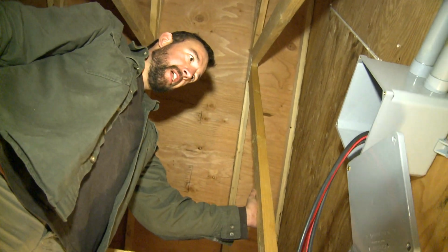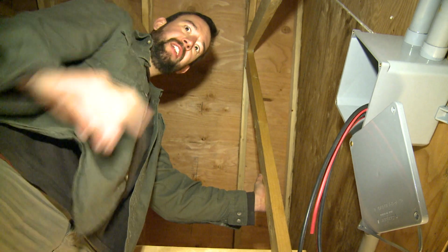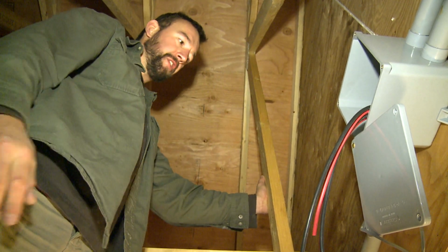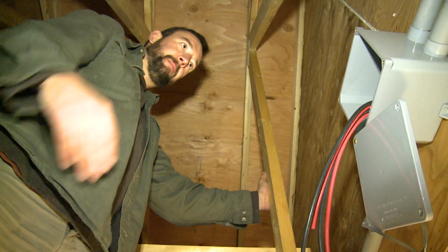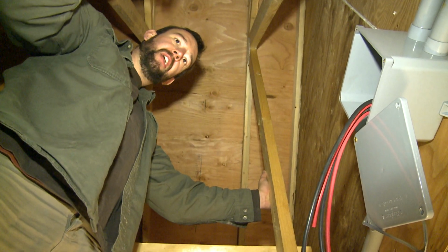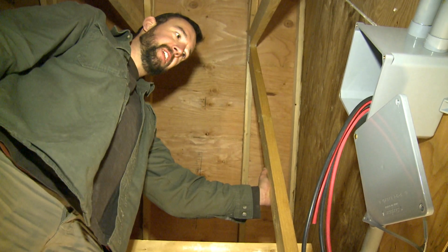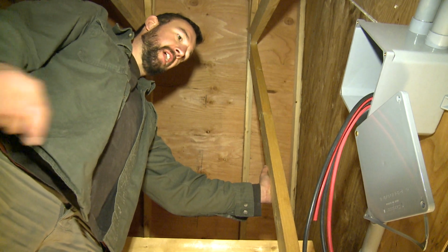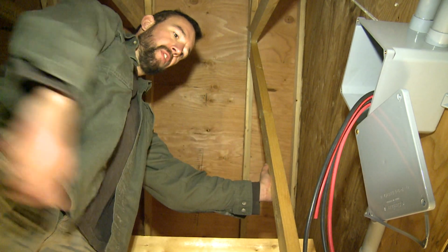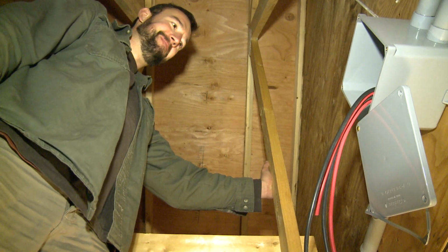This is our main parallel junction point from the array down to the inverters. So we've stepped up to a larger cable here to accept the 3 parallel strings from each array. Therefore, we can use fewer conductors and have a nice cleaner set of runs into the inverters. And it's a good safe place for them.